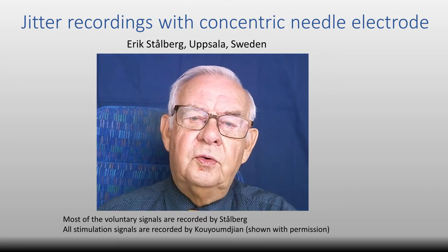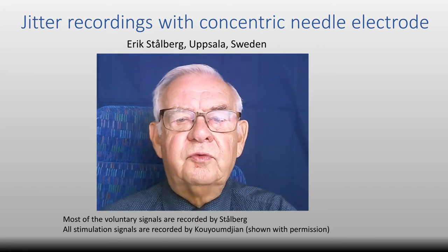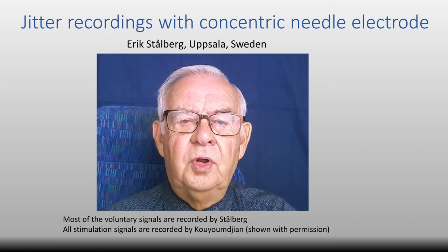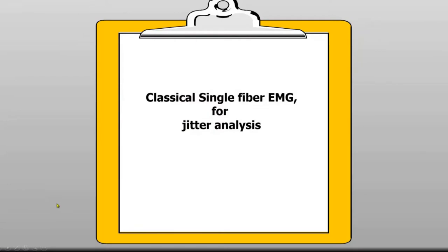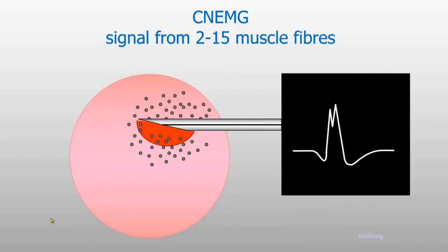In this video we are going to discuss the use of concentric needle electrode for the recording of jitter. But first, a few words about the classical single fiber EMG and some of its principles. Here is the recording area of a concentric needle electrode, and there were many fibers here to be recorded, which was not a good idea to obtain activity from just one muscle fiber.